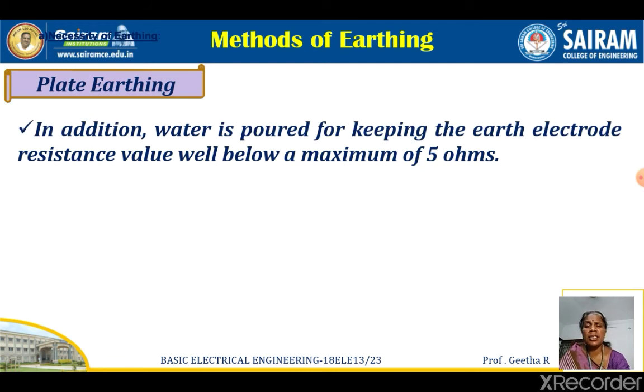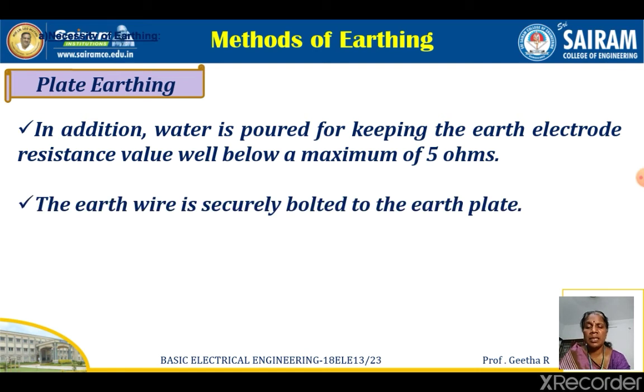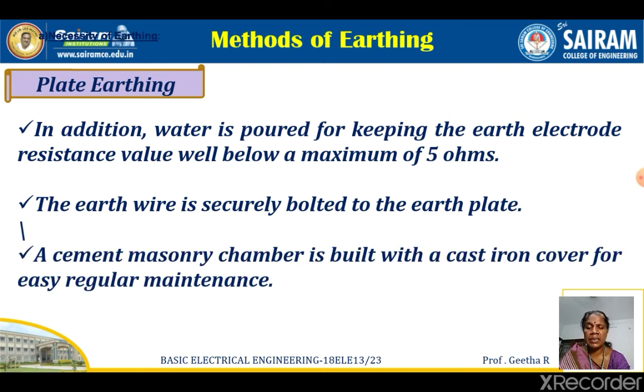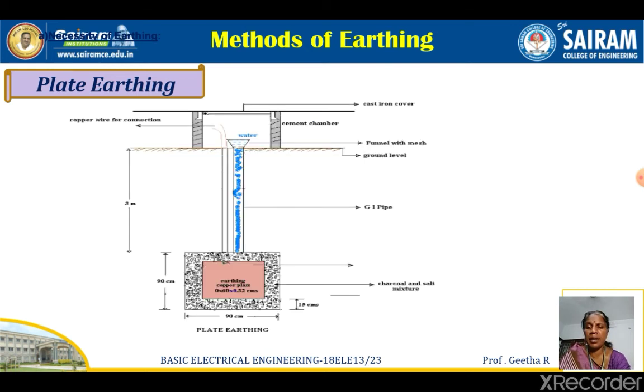In plate earthing, in addition, water is poured to keep the earth electrode resistance value well below a maximum of 5 ohms. The earth wire is securely bolted to the earth plate. A cement concrete chamber is built with a cast iron cover for easy regular maintenance of this apparatus. You see here the diagram of plate earthing. This portion is the concrete chamber. You can see the iron cover here. This can be removed for easy maintenance.